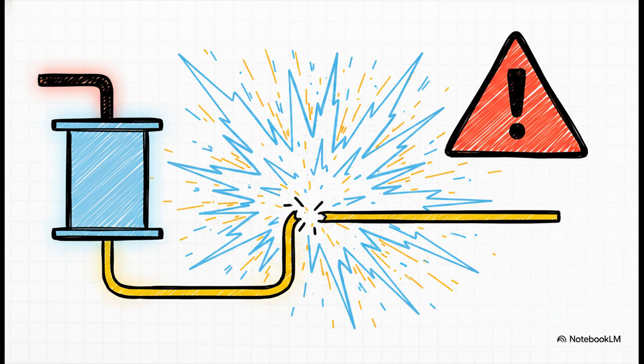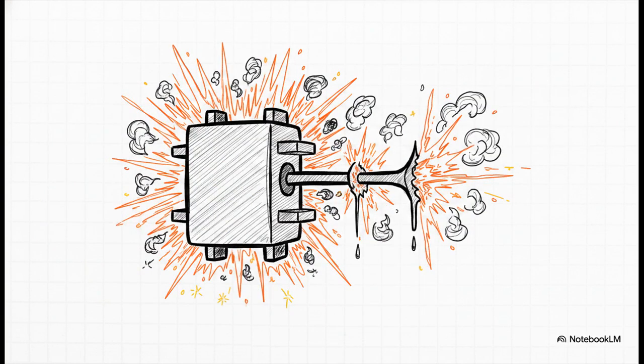Never open circuit a current transformer secondary while the primary is energized. Because CTs are proportional current devices, they desperately want to push current. It's what they do. If you break that secondary circuit, the voltage spikes instantly to try and bridge the gap. We're talking about dangerously high voltages that will cause severe equipment damage and put absolutely anyone nearby at a massive risk. Now, contrast that immediately with rule number 2.